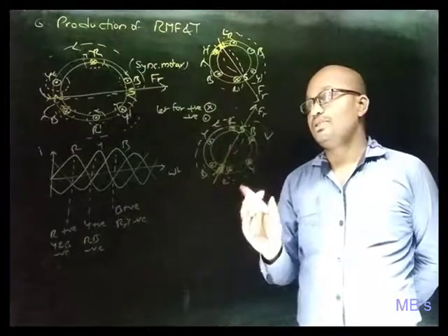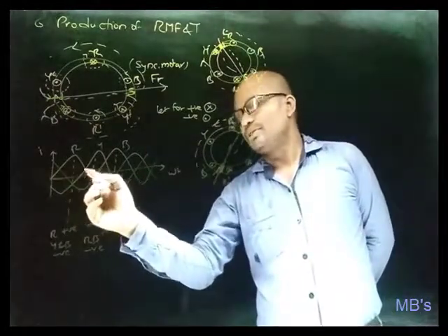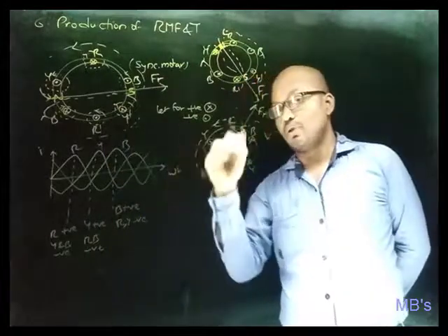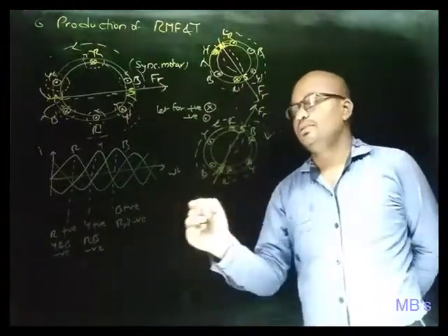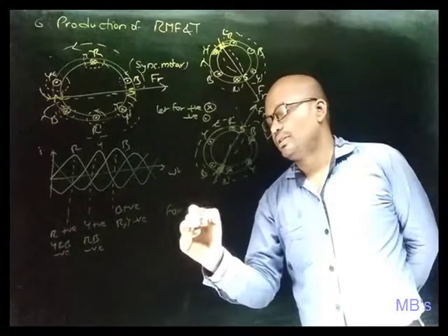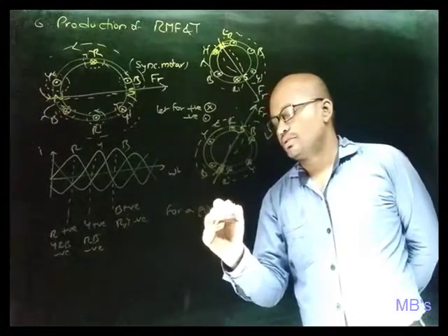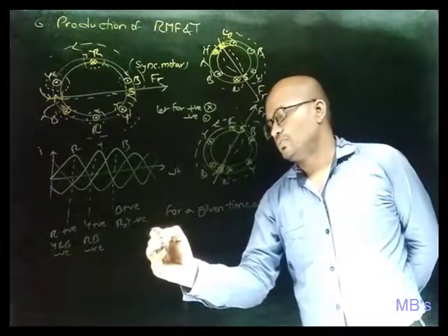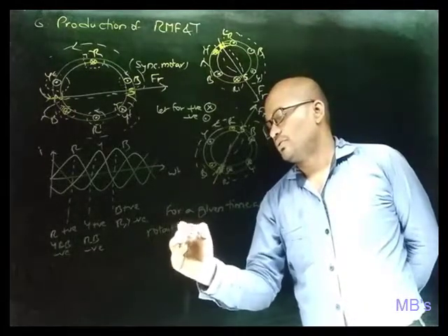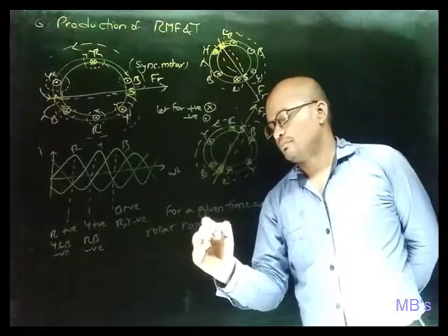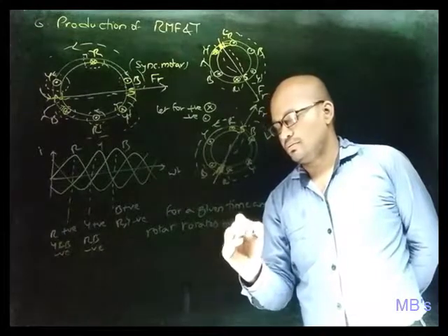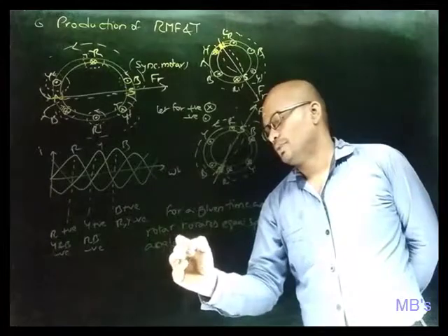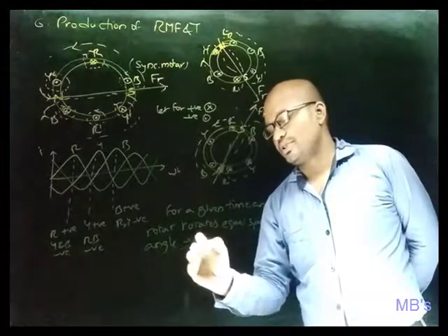From this, what you have to observe is that for a phase sequence of R-Y-B, the rotating magnetic field is clockwise. For a given time angle, the rotor rotates an equal space angle, which implies the rotor rotates at synchronous speed.